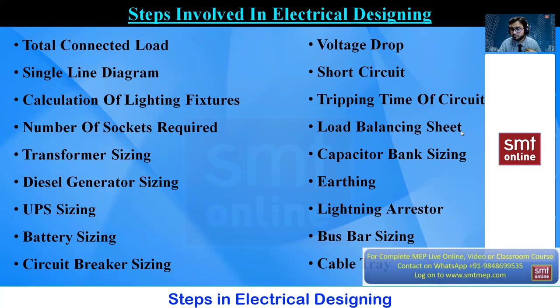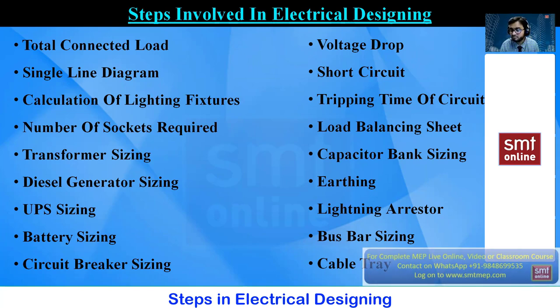The main backbone of the design is the load balancing sheet, where we balance the load equally among all three phases. We also have capacitor bank sizing to improve the power factor, earthing to maintain earth resistance value and propose the number of earthing pits, lightning arrester for projects in hilly or coastal areas or high-rise buildings, bus bar sizing for high current carrying capacity instead of cables, and cable tray sizing for large cables.